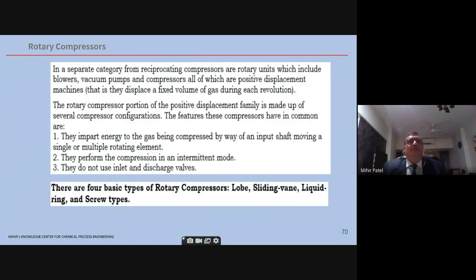Now, rotary compressors. So rotary compressors are 4 different types: lobe type, sliding vane type, liquid ring, and screw types. The sliding vane also can be used as a vacuum pump. Liquid ring type is also called LRVP, liquid ring vacuum pump. So liquid ring type is a very good vacuum pump also. Okay. So these are the rotary compressors.